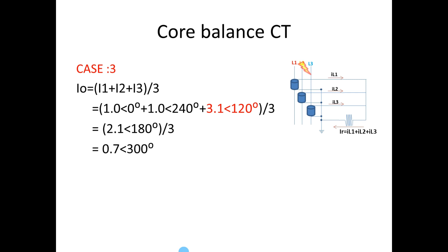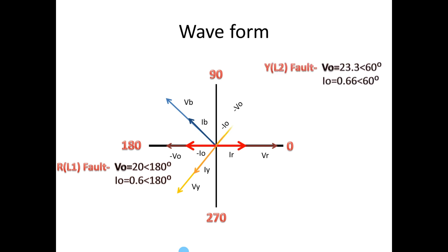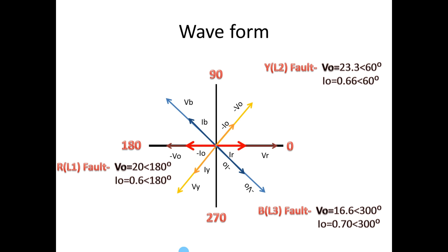Now I am going to use all the noted values of voltage and current and plot them in a power system phasor diagram. In a power system diagram, R phase starts at 0 degrees, Y phase starts at 240 degrees, and B phase starts at 120 degrees. For R phase fault I got 180 degrees, which is directly opposite to that phase. For Y phase fault I found 60 degrees, which is also directly opposite to its phase. Similarly, for B phase fault I got minus 60 degrees or 300 degrees, which is directly opposite to its main phasor angle. From this we clearly understand that the earth fault current will be opposite to the phasor current.